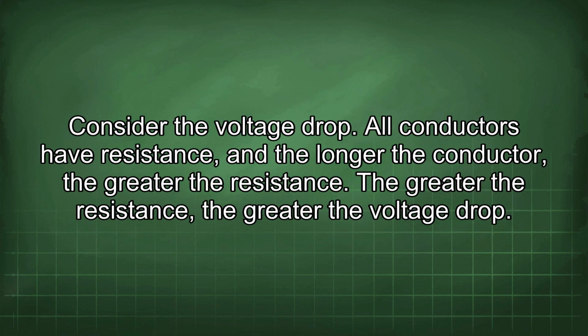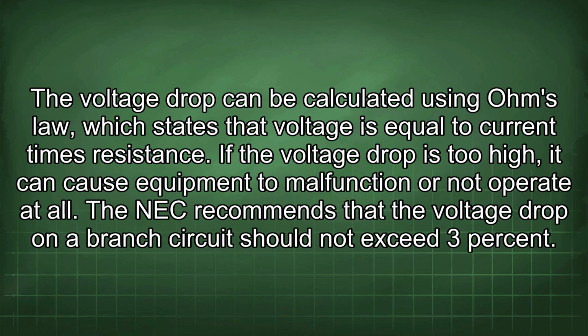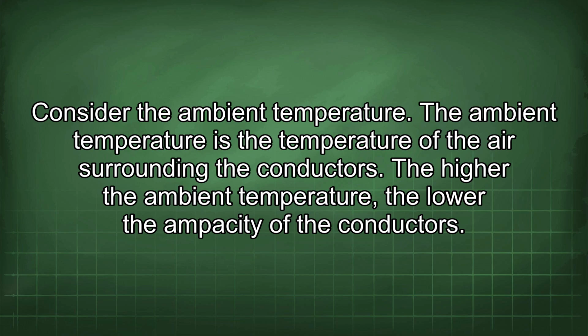Consider the voltage drop. All conductors have resistance, and the longer the conductor, the greater the resistance. The greater the resistance, the greater the voltage drop. The voltage drop can be calculated using Ohm's law, which states that voltage is equal to current times resistance. If the voltage drop is too high, it can cause equipment to malfunction or not operate at all. The NEC recommends that the voltage drop on a branch circuit should not exceed 3%. Consider the ambient temperature.